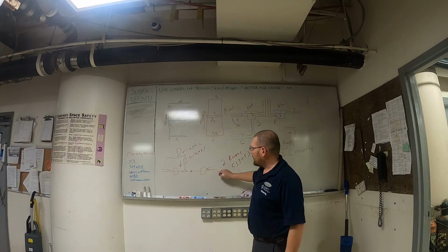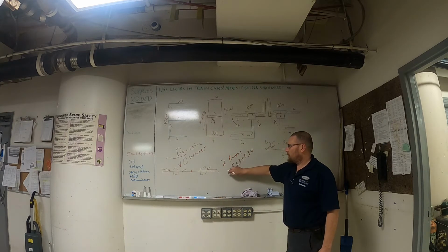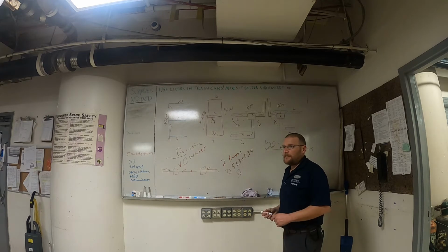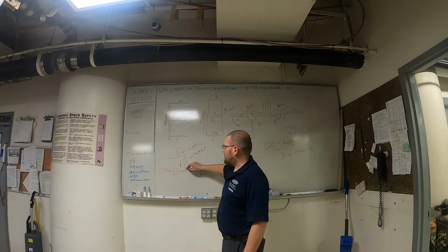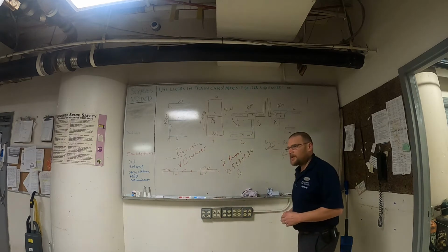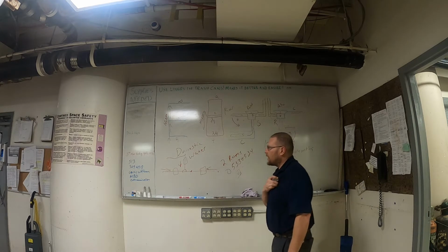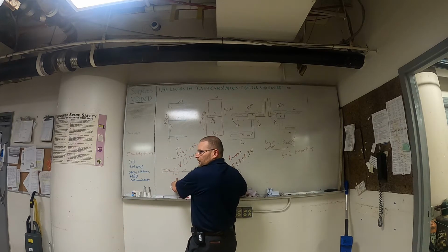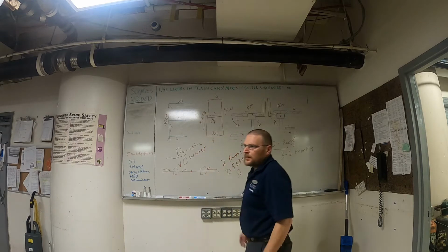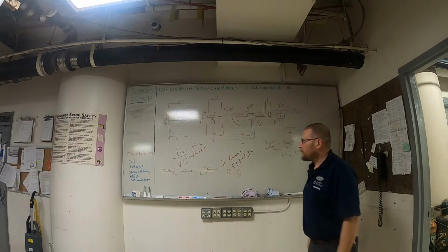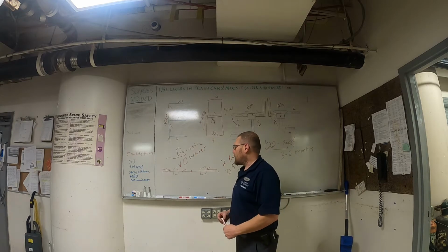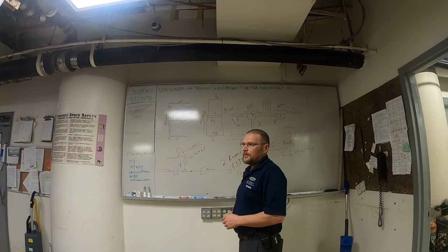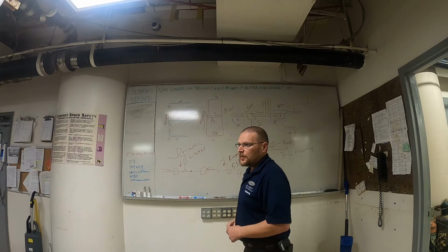Now, if the leak was back here on just the straight run of long pipe, you would only have to close 2 valves. The only time you're looking for 3 valves is if you're going up, if the T is involved. And sometimes you have to go back, because these 2 valves may have quit working. You may have to go out and find the next 2. So you always go in pairs of 2. And a lot of times with these recircs, especially here, you'll hear the water shut off, because you can just hear it running through the pipes.